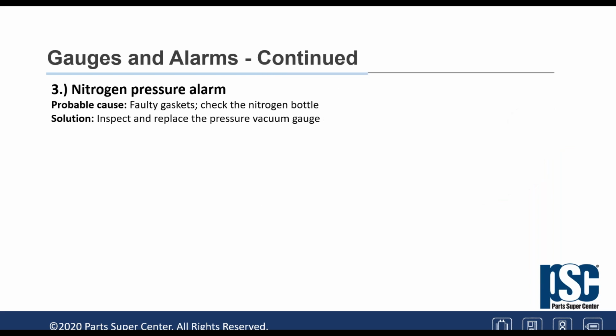The nitrogen pressure alarm, this is a case where a transformer has a nitrogen blanket on the tank. To prevent the atmosphere from touching the oil, we put the nitrogen blanket. Nitrogen is an inert gas that does a beautiful job. Now, the nitrogen pressure gauge should work in response to what's happening in the main tank. If the main tank has high pressure, then the vacuum gauge should bleed out the excessive pressure. If there is a vacuum, then the gauge should let the nitrogen go inside the tank. In other words, there should always be a blanket of nitrogen in the tank. And if that doesn't happen and it acts funny, it is because something is wrong or the adjustment in the gauge is inappropriate.